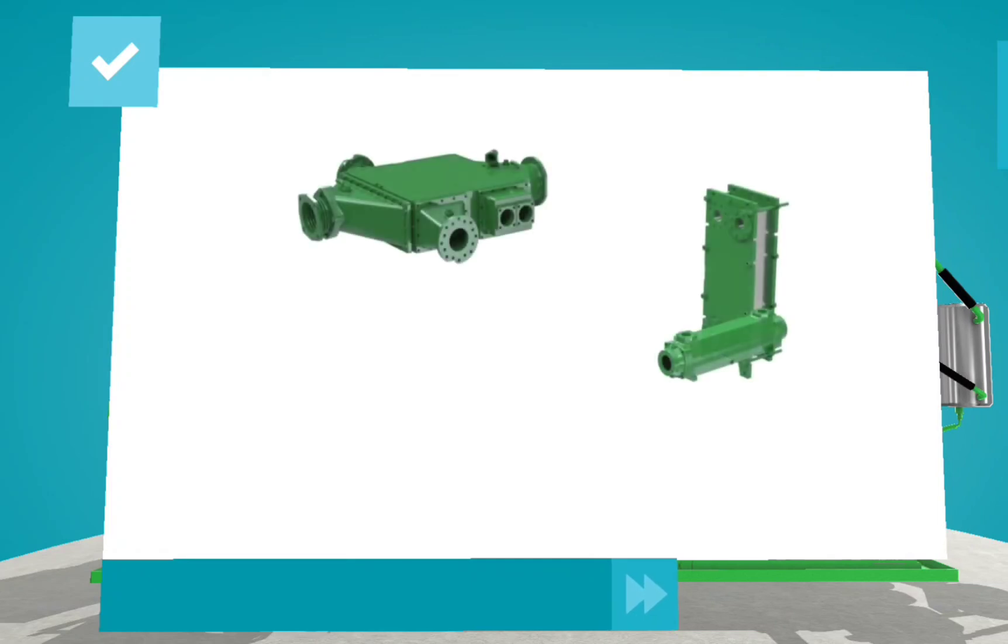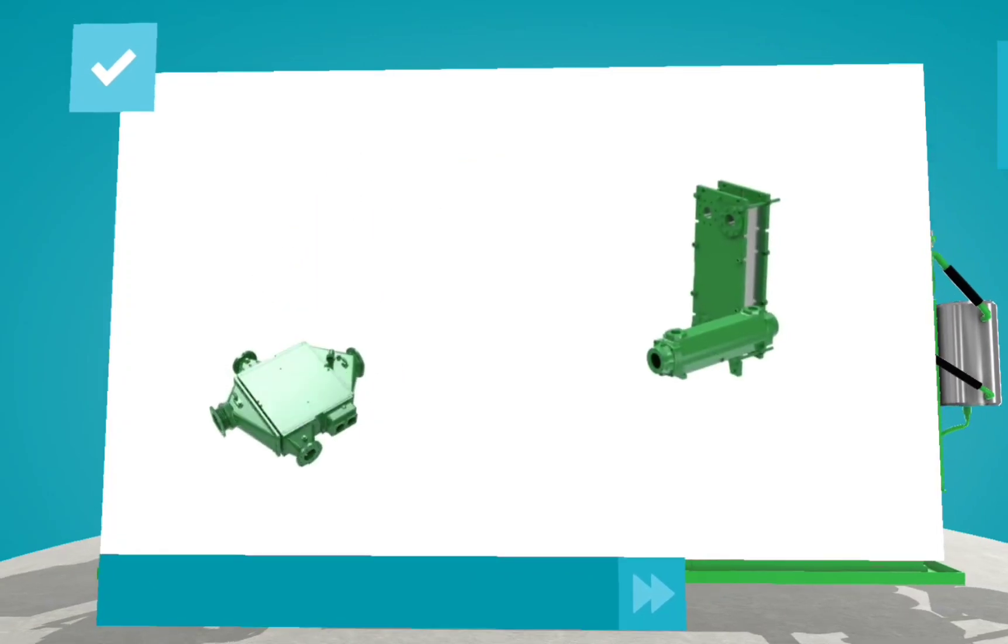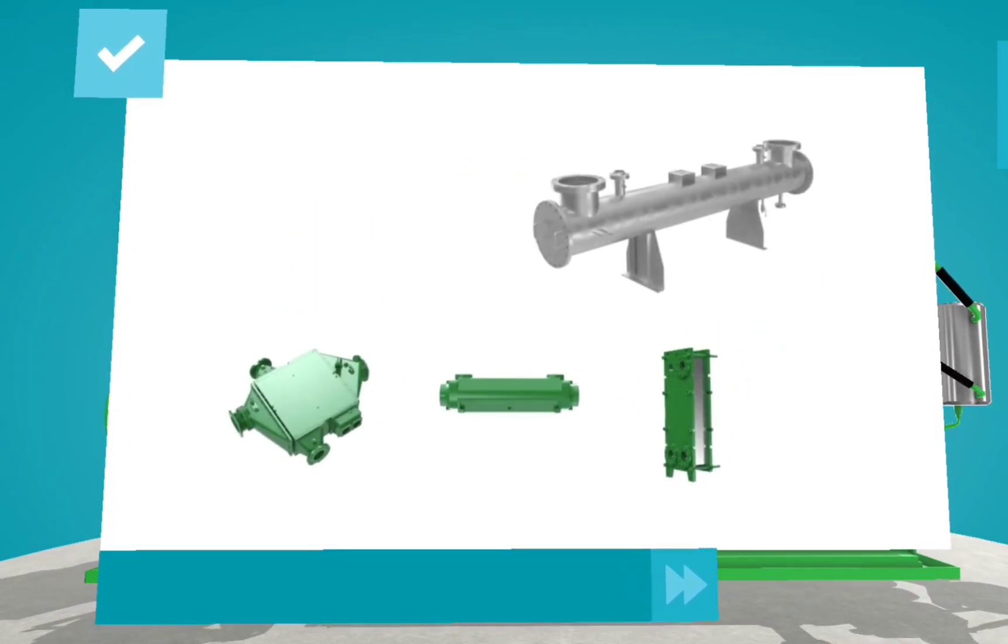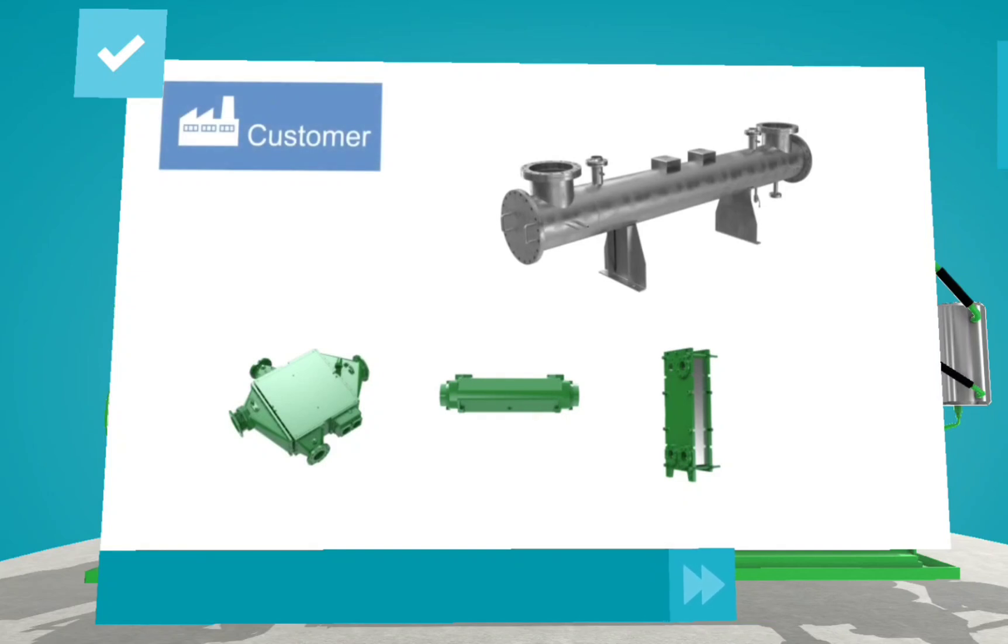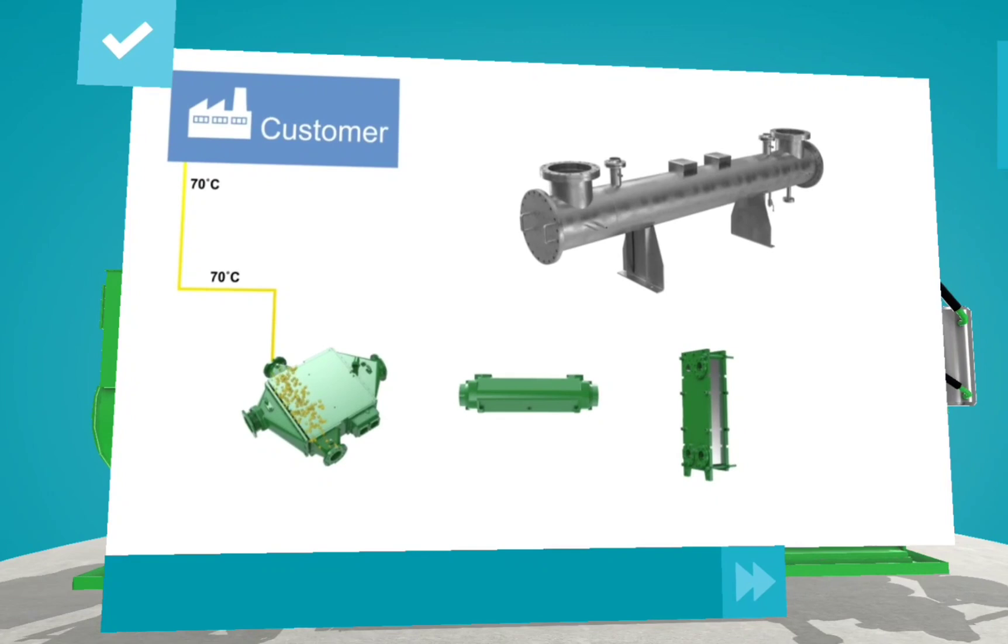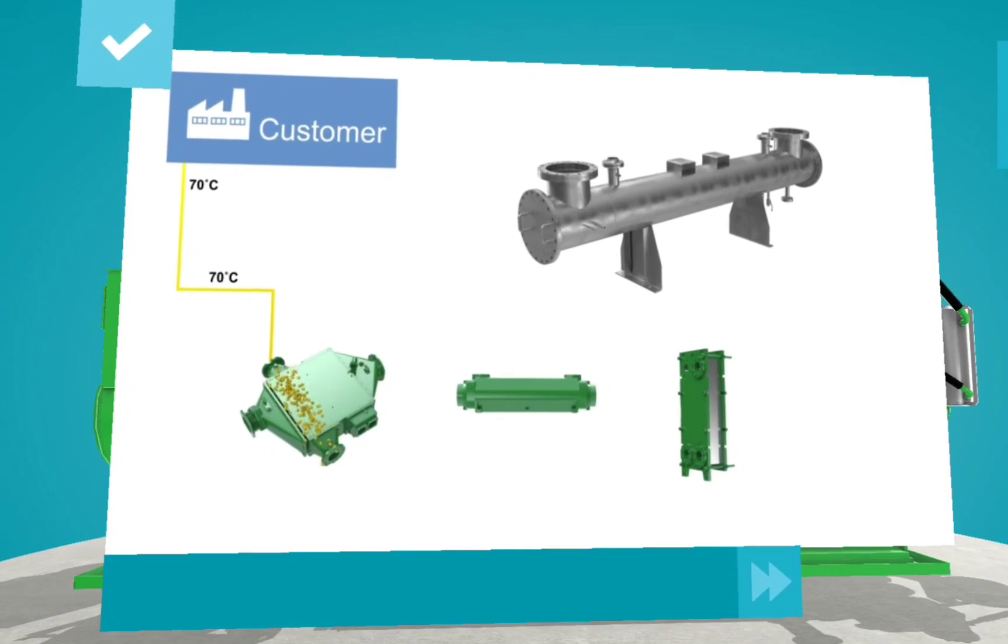In addition to the heat exchangers on the engine, heat can also be recovered from the combusted gas with an exhaust gas heat exchanger. Heat exchangers are connected with piping in a specific sequence, which can be modified to meet each customer's individual temperature requirements.